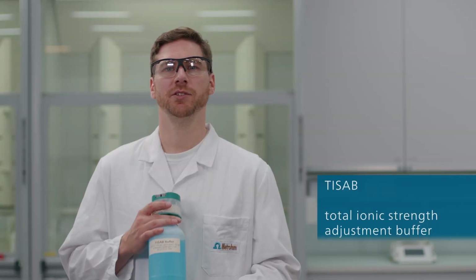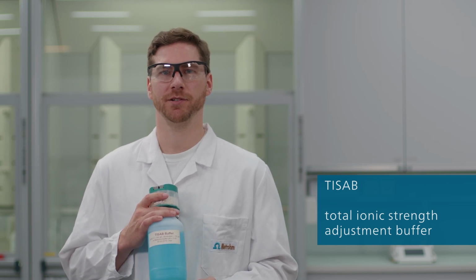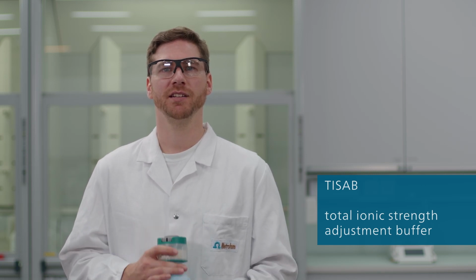It's important to note, for both measuring modes, you need to add total ionic strength adjustment buffer, TISAB for short. This buffer fixes the pH and the ionic strength. We recommend plastic labware for all measurements, as glassware can falsify the result.